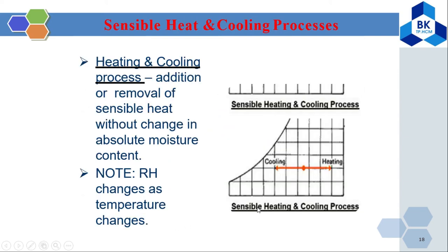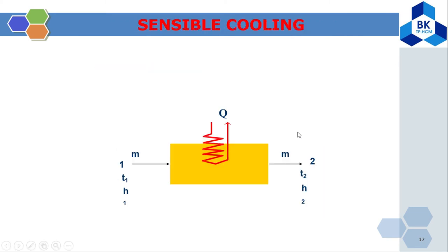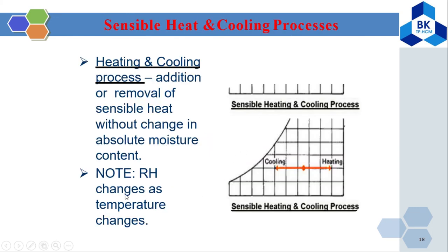Sensible cooling is the opposite procedure to sensible heating — heat is removed, but the amount of water in the air does not change. The sensible heating and cooling process involves addition or removal of sensible heat without change of the absolute moisture content. Note that although the absolute humidity does not change, the relative humidity does change as temperature changes. On the psychrometric chart, heating moves to the right and cooling moves to the left.